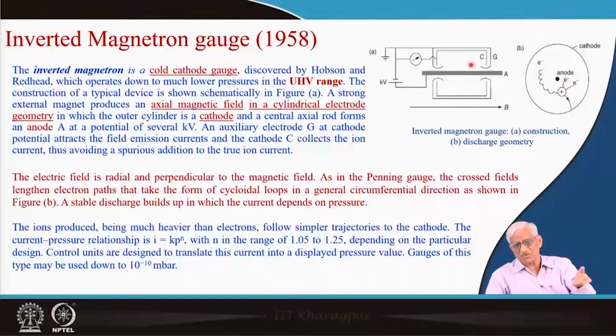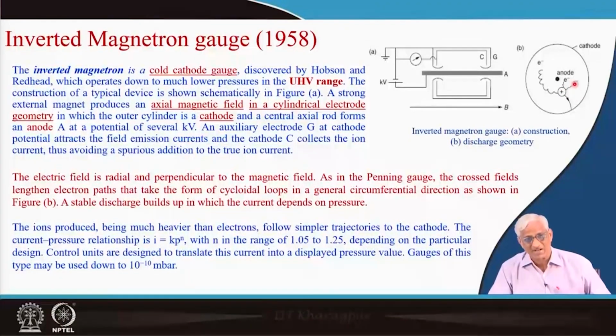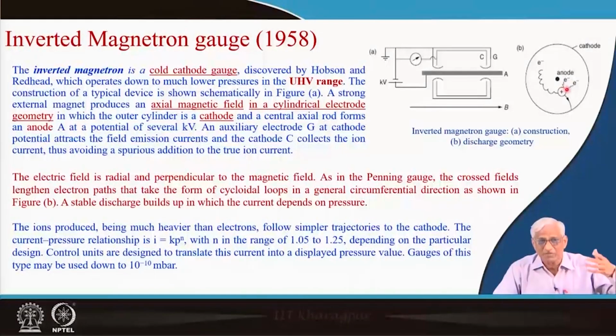There can be another structure, you can do varieties of gauges, and another calibration constant will be there for the ionization cross section with the atoms by these field emitted electrons. Initial electrons are very few. So, one electron, once it ionizes, 2 electrons are there, but this electron came out of the atom, but it has lost its identity. That is also, it looks like a field emitted electron. So, both of them will be accelerated by the electric fields, both of them will be confined by the magnet. So, it will be a runaway process, after some time equilibrium comes.